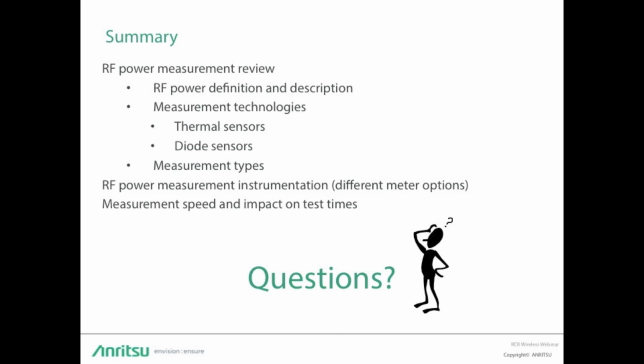When determining the measurement uncertainty, how do I pinpoint which factors are having the greatest impact? As we discussed earlier, the different factors that come into play with measurement uncertainty will vary depending on the type of measurement you're making. When you're looking at a higher power measurement, for example, that's where your mismatch uncertainty is going to come into play more. That's why when we design our sensors at Anritsu, we work very hard to make sure that we are extremely careful and accurate in our matching protocols. And when you get into the lower measurements, that's when you're going to start to see more of the zero set and drift effects, the noise of your test signal, those kinds of things. The important thing here is that if you use the measurement uncertainty calculators that we provide, you can enter in all the parameters of your measurement and get a good confidence level in what your measurement uncertainties will be.